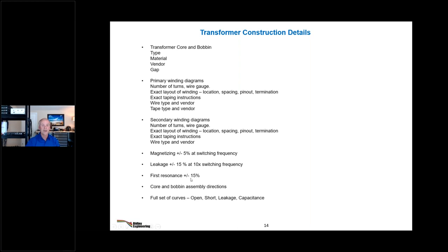I wanted to see the first resonance within plus or minus 15%. The vendors like to specify the first resonance as a minimum, which means they could wind it totally differently elsewhere and it wouldn't be there anymore. Instead, they keep it in the same place, within 15%.